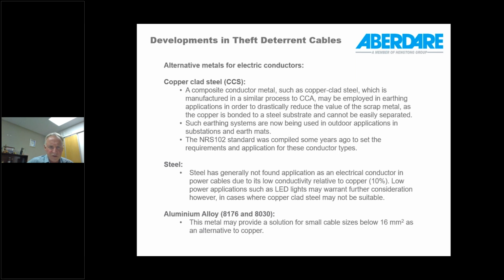Steel is an option, but due to the properties of steel, it's really not found application as an electrical conductor in power cables. Of course, it has a very low conductivity relative to copper, about 10%. But potentially these could be used in very low power applications, for LED lights, for instance.